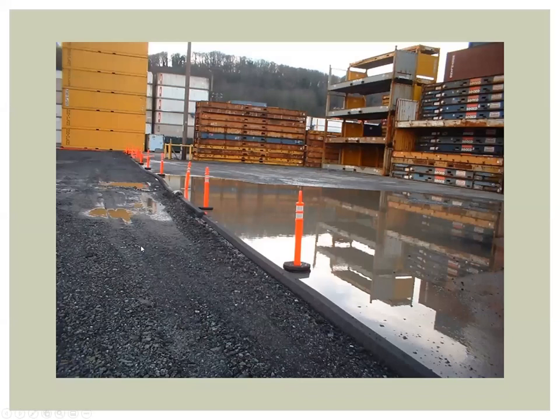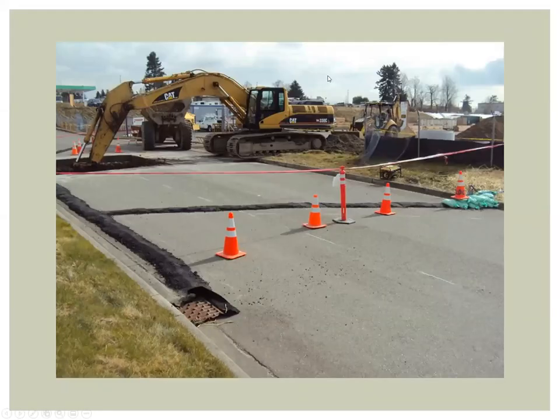Here's an example — work area to the left, with asphalt replacing a non-work area to the right. Water on the right doesn't have to be dealt with. Another example is a utility connection project where they've used asphalt berms to divert water from the road surface to the left, keeping it out of their project area and directing it to the curb line and into a catch basin. Any water that ends up within the berm perimeter drains to one corner, where a small one- to two-inch pump sends it back into a hole they dug on site. Same for water pulled from the excavation — it's pumped back into an area within the project.